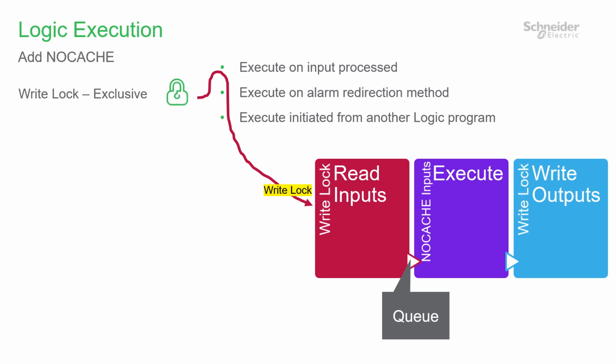When inputs are read during the write lock, you should avoid the kind of inputs which can take some time to evaluate. Specifically, these are SQL queries and historic data retrieval. Naturally, you should keep these kinds of demanding operations to a minimum, avoiding them if possible.